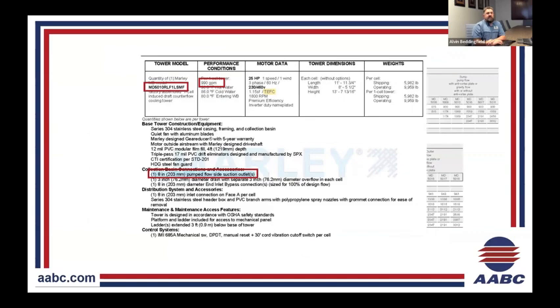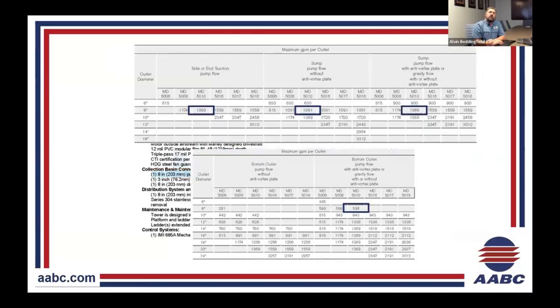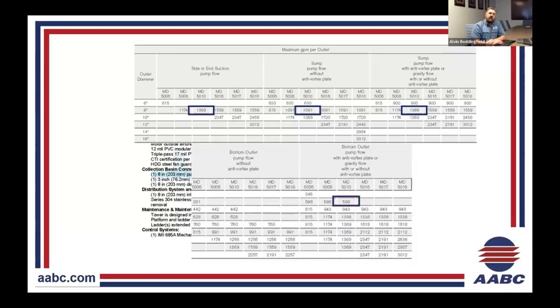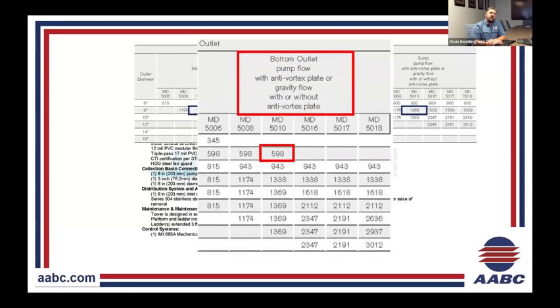But looking at the suction side of what the collection accessories were, it was an 8-inch pumped flow size connection. Going into the 5 scenarios of what we can do, we were sized at the top one, the side end suction, but that's not what we had. Going through each scenario is like taking a snapshot: what do we have, what's installed? So isolated down was the bottom outlet pump flow.